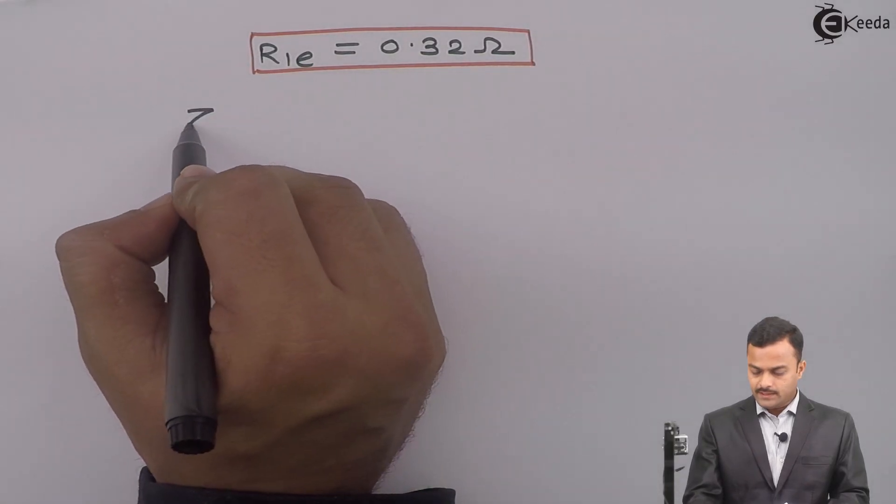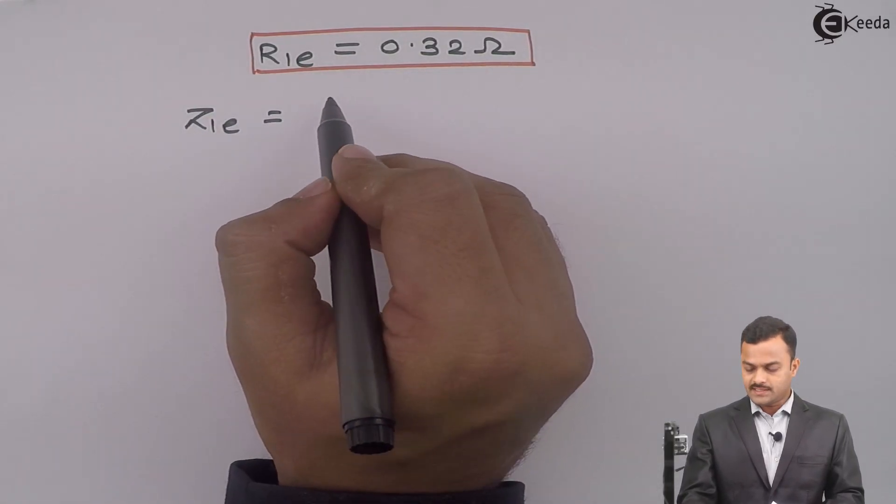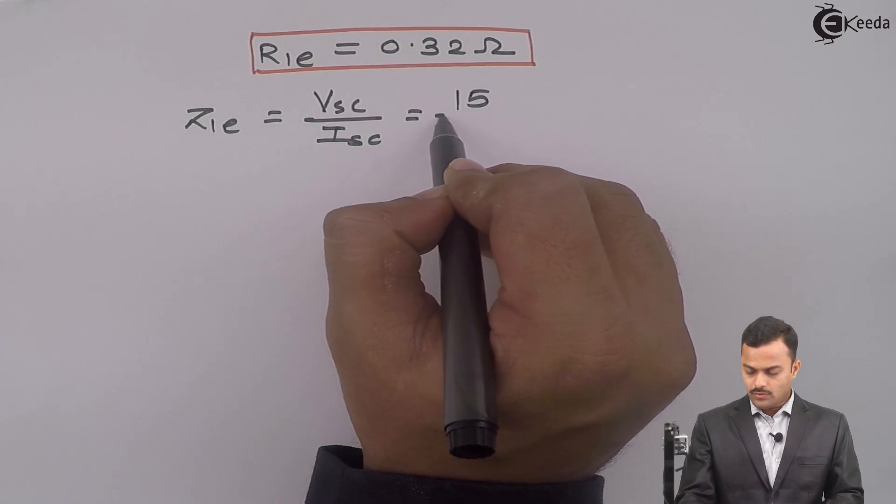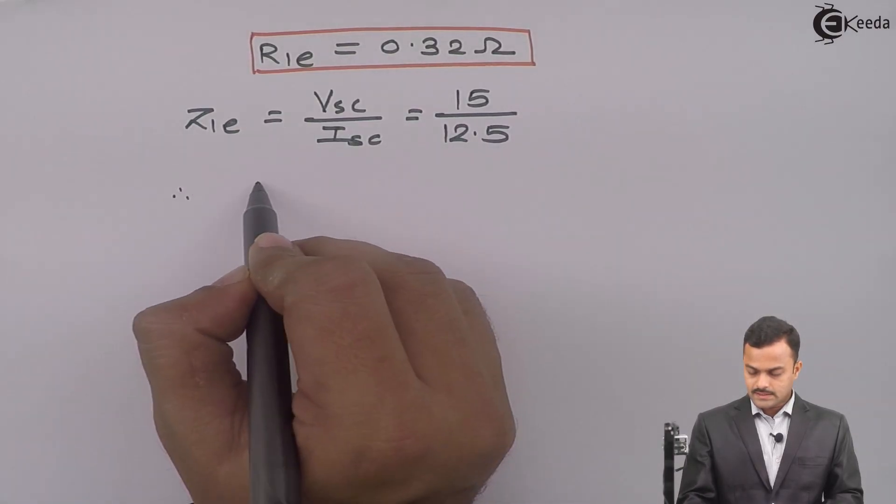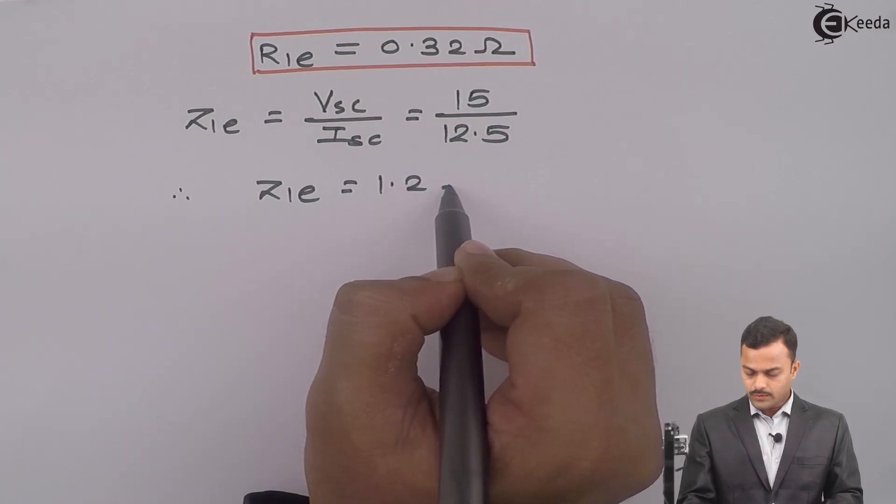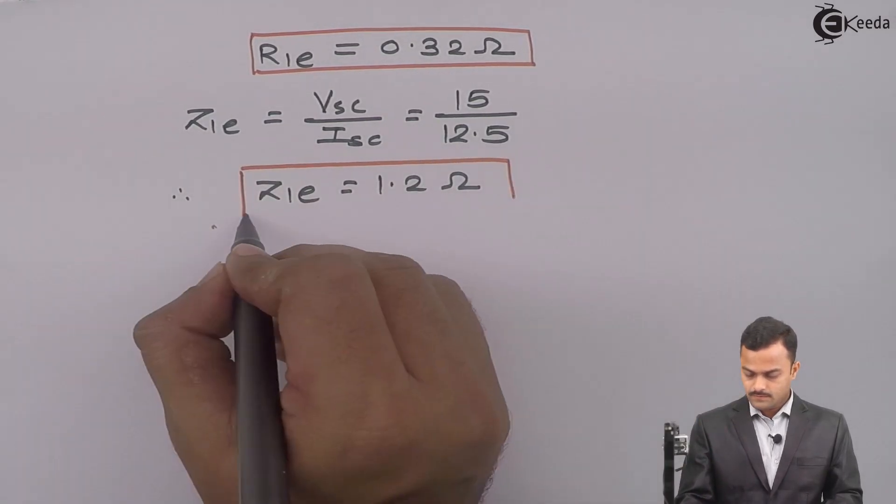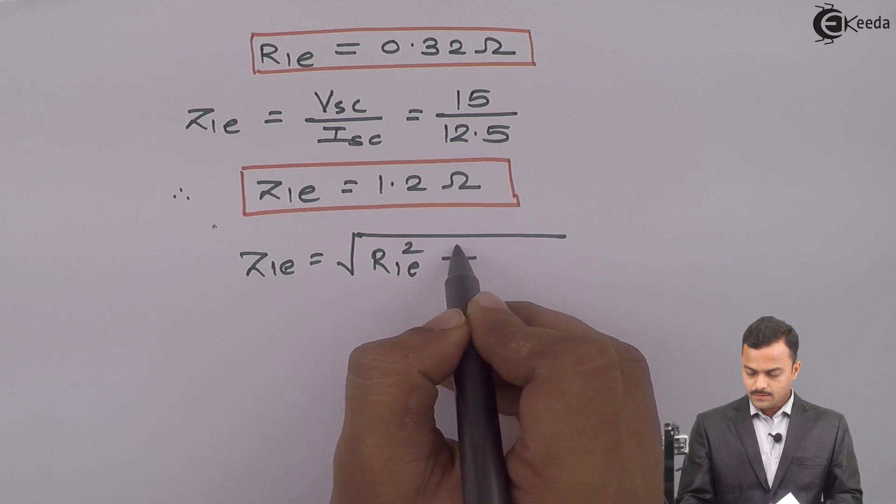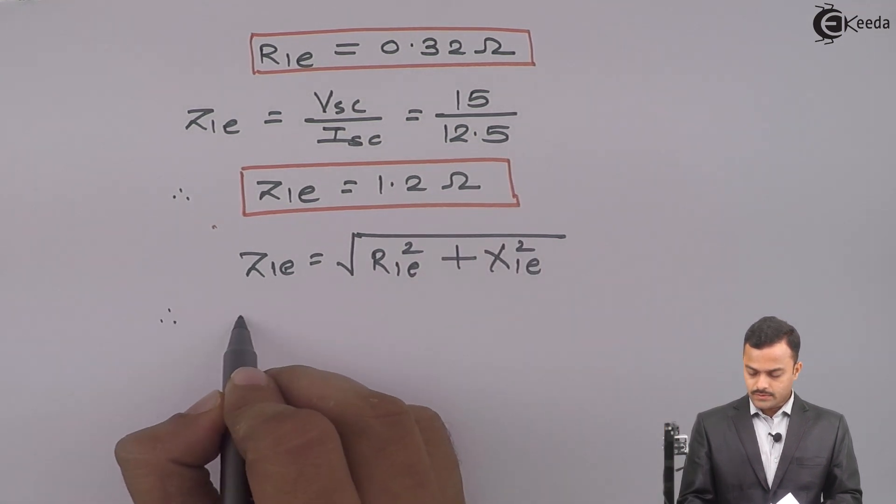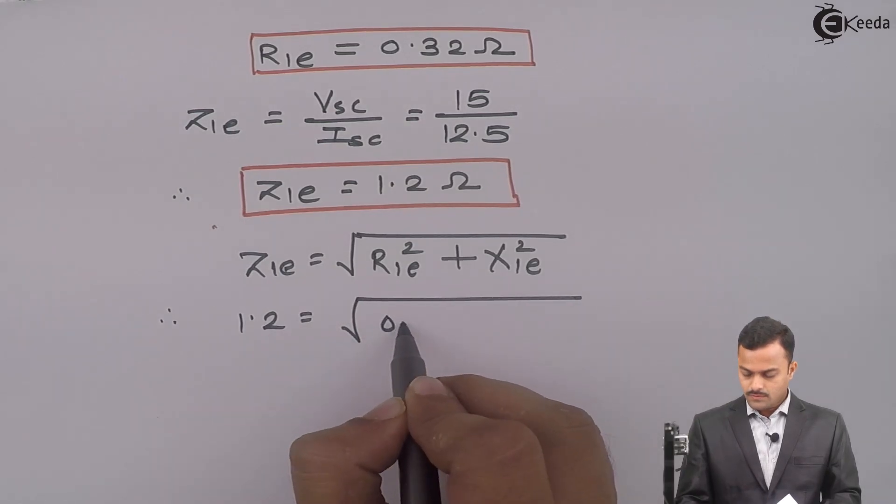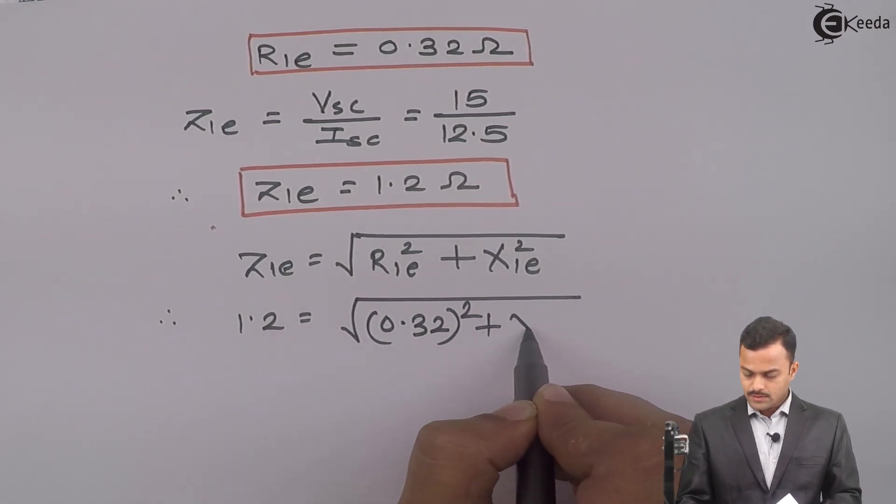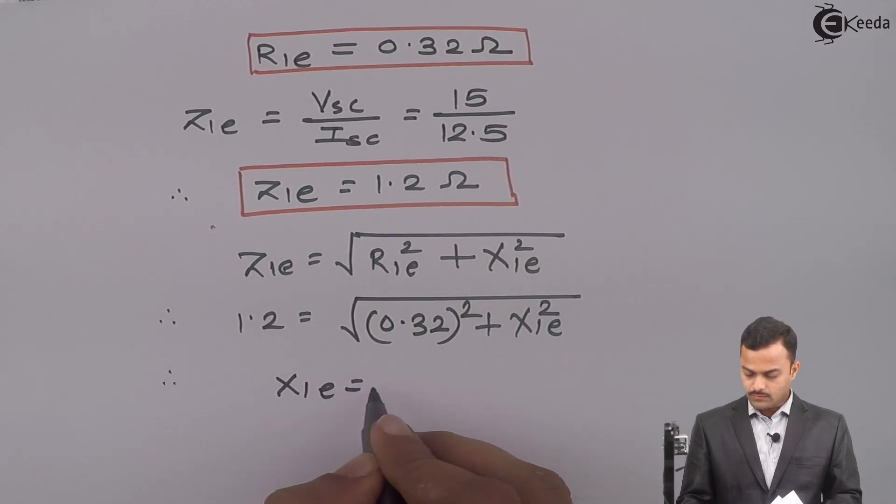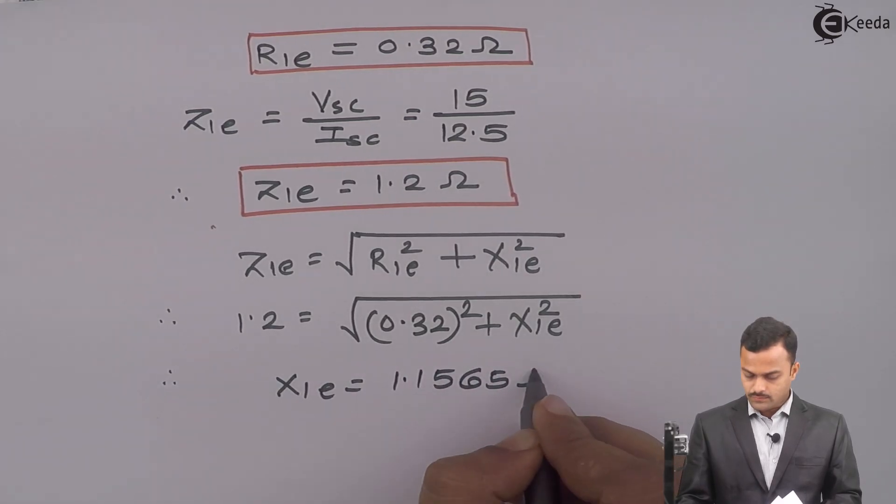Now, Z1E impedance referred to primary side is VSC upon ISC, 15 upon 12.5. The answer you will get is 1.2 ohm. Z1E is nothing but root of R1E square plus X1E square. So, it is 1.2 equal to root of 0.32 square plus X1E square. So, the only unknown is X1E and you will get X1E equal to 1.1565 ohm.